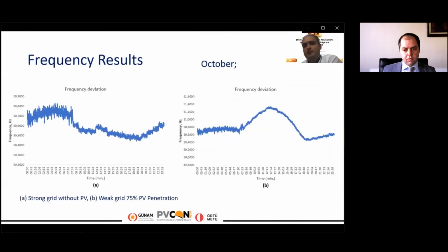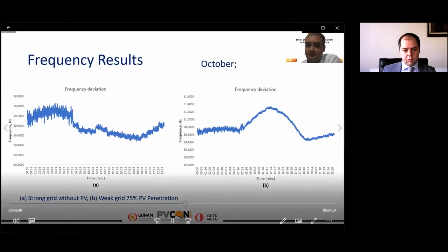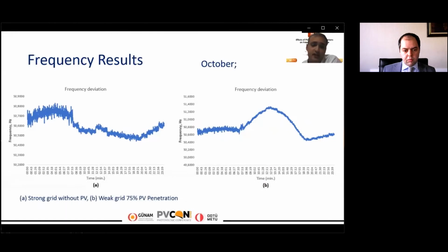When we look at the month of October, here is the minimum consumption, minimum demand. We saw the frequency deviation exceeds the 1% limit, but slightly. As you can see, figure A, here is the strong grid without PV, and figure B, weak grid at 75% PV penetration. The frequency is going lower when the demand is high, but frequency goes higher when the demand is low. It can be seen in both of the figures.